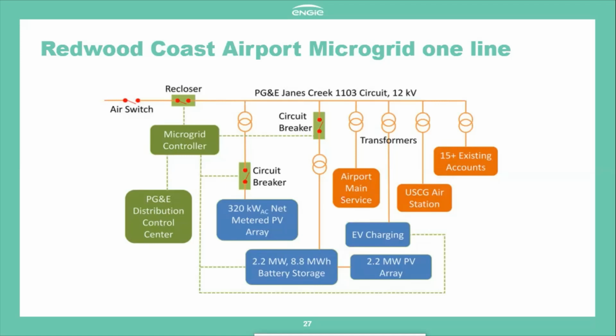But if you have specialized equipment that shuts off in milliseconds, you need a solution that allows for that ride-through so key equipment doesn't shut down. The case I mentioned about the quartz manufacturer — if we were over 300 milliseconds, that equipment would shut down and cause a problem.